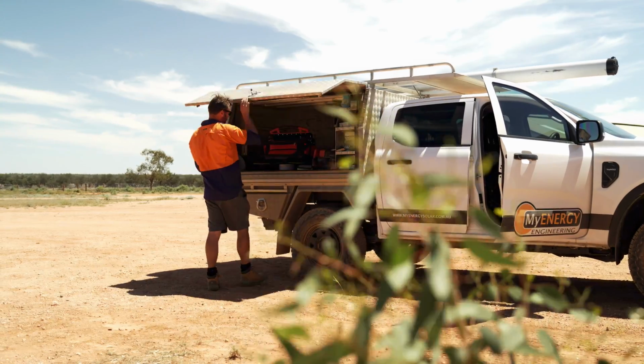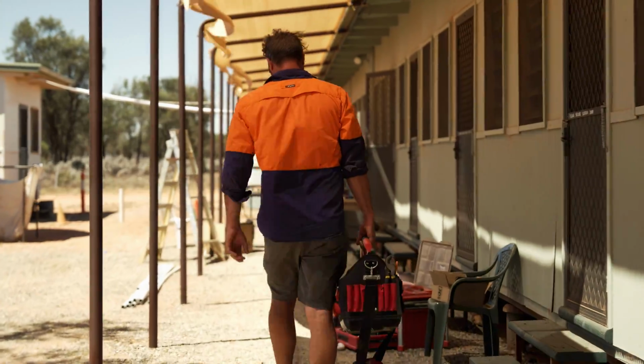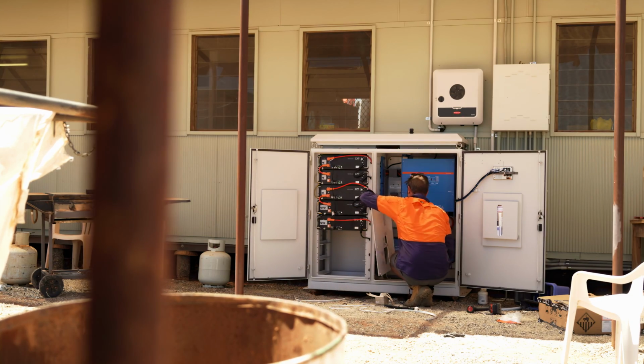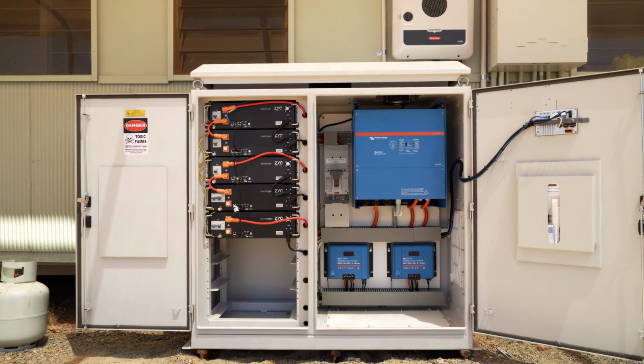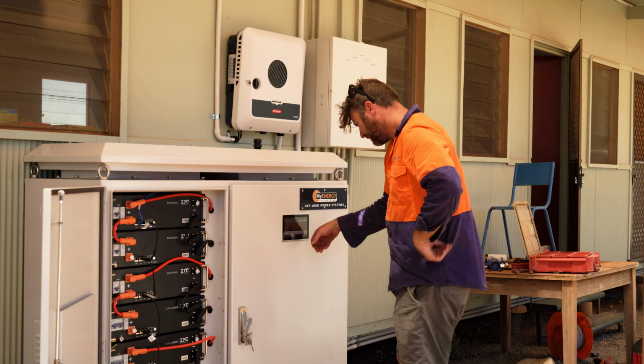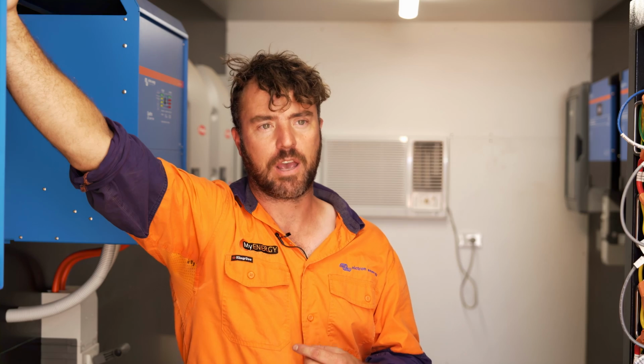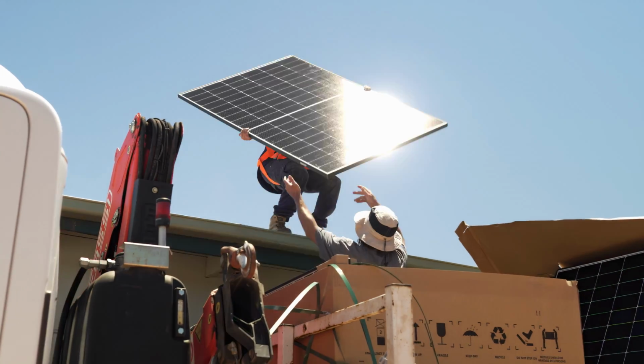Same with the smaller system over at Shearers Quarters. It's a smaller system, built in a pre-made cabinet and fitted out in our workshop, so all we really need to do is drop it on site, run our solar and AC cables into it, and it's good to go. Got a 15 kVA inverter out there, 25 kilowatt hours of battery storage, and 12 kilowatts of solar on the roof.